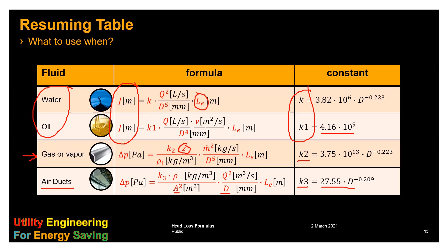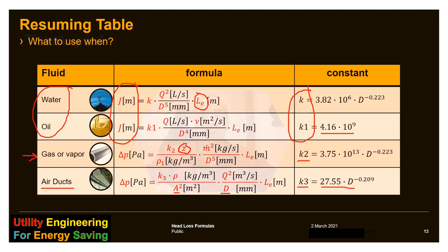For gases, vapors and any other fluid, either condensable or not, we can use the third row, where zeta is the compressibility factor. If the gas is ideal, zeta is 1, and K2 is given by this empiric formula. If the pipe is not round, which is mostly the case of the air ducts, then we need to use the fourth formula, where the area of the pipe and the hydraulic diameter are expressed respectively in square meters and in millimeters. And the K3, the constant, is given by this empiric formula. The equivalent length is present in any formula and is considering the sum of the actual straight length of the pipe plus the artificial length due to the fittings, and those values are given by manufacturers of the corresponding fittings.